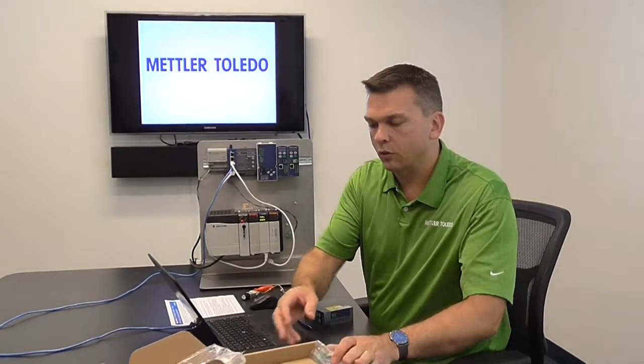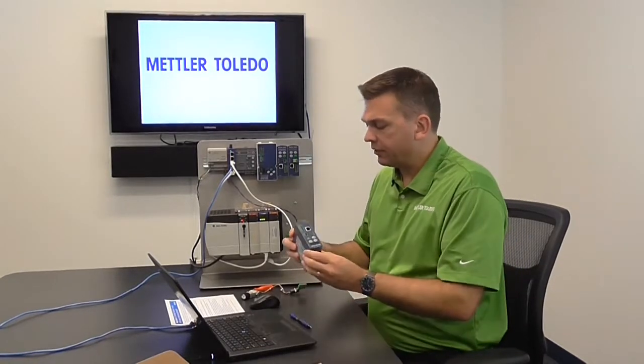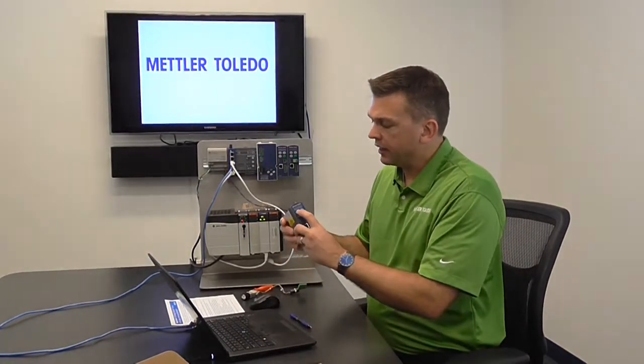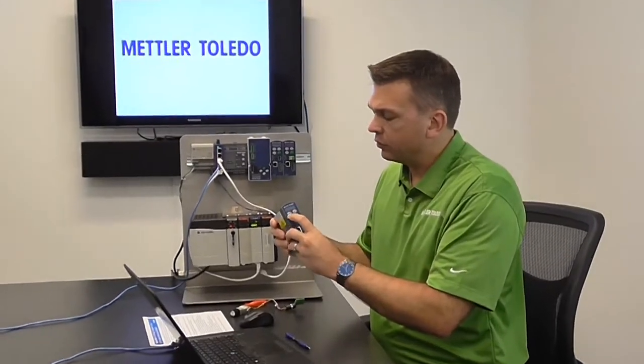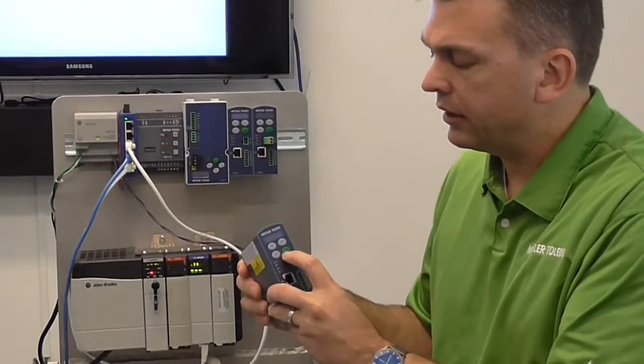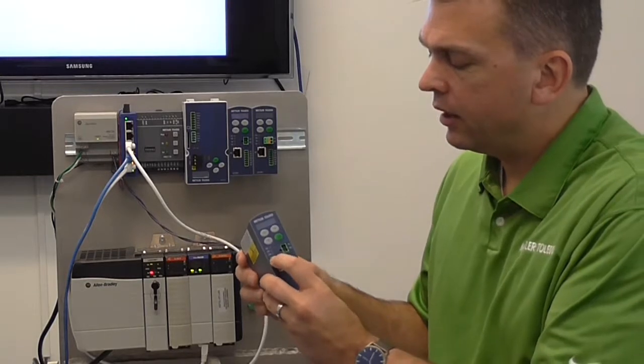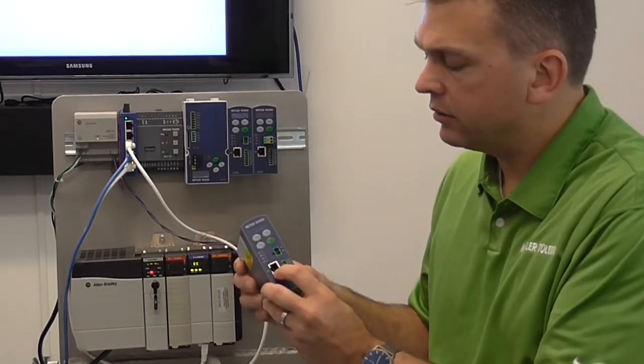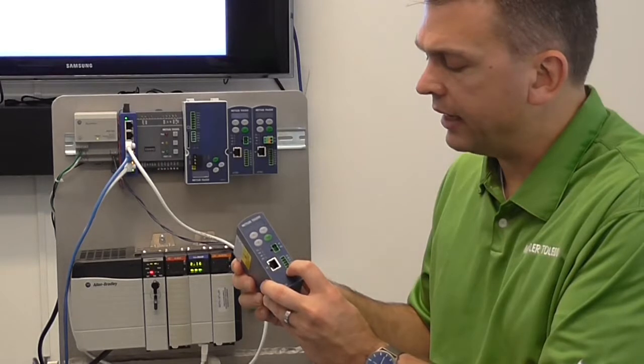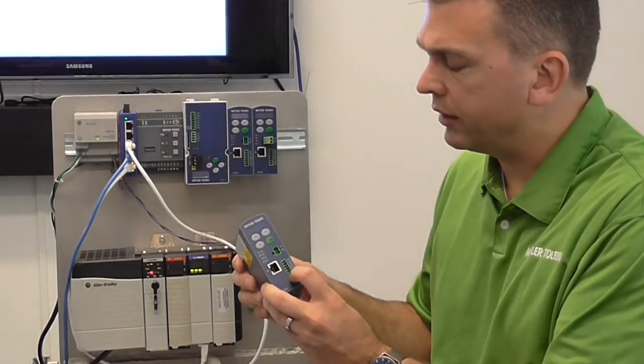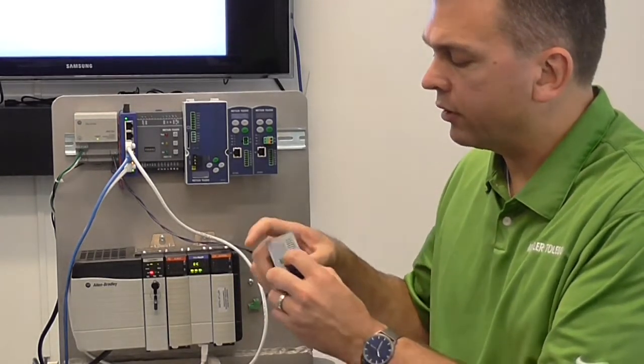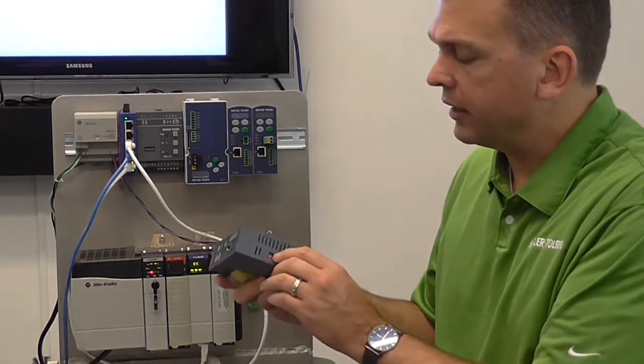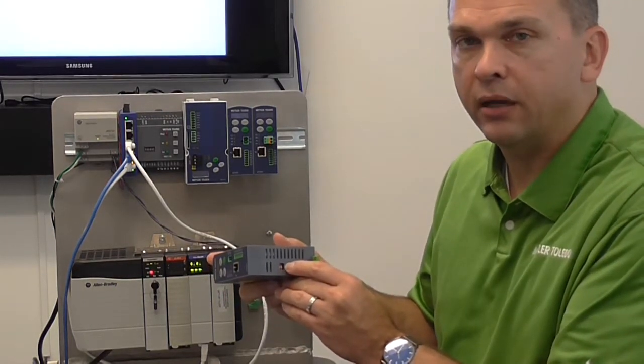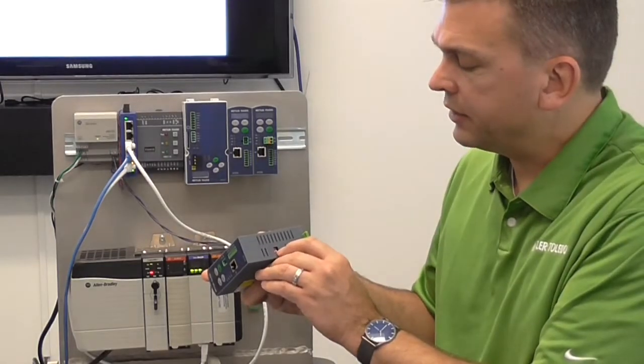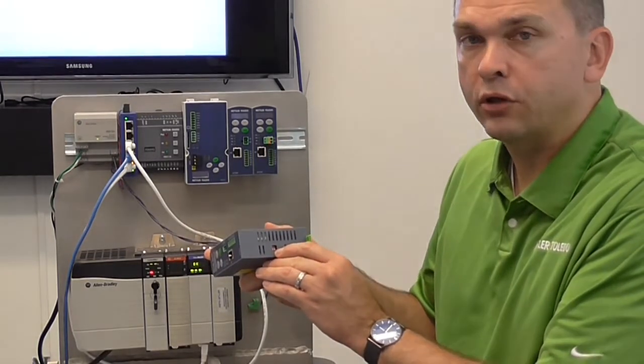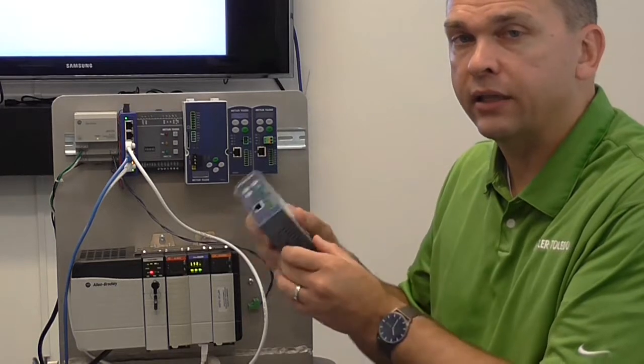All right, so if we look at the ACT350 itself, we see that it's got a display that we'll see in more detail momentarily, membrane keypad, LEDs, power input, network input, and it has the analog load cell input, as well as programming port and reset. If you ever need to reset this to factory settings, take dip switch number 2, turn it to on, reboot the device, and it'll reset.